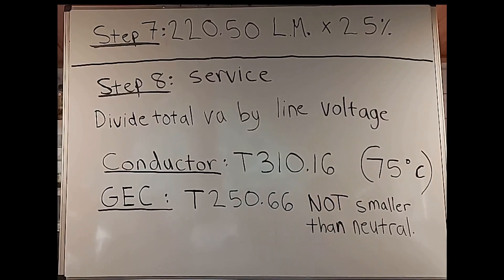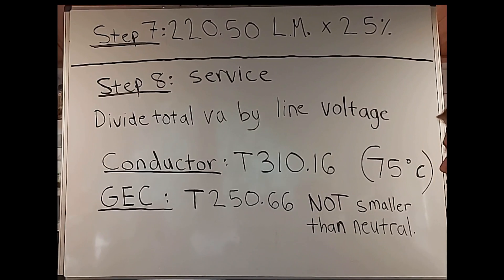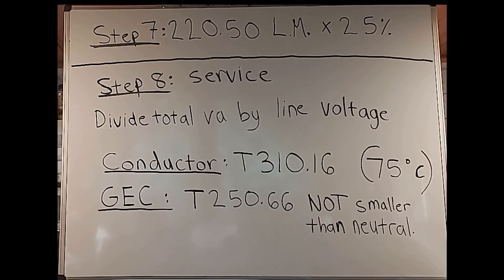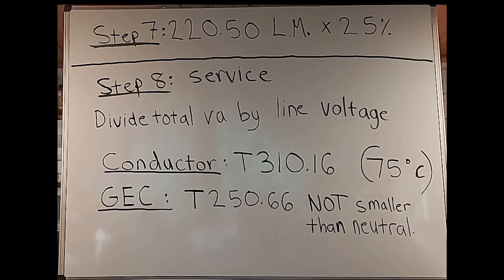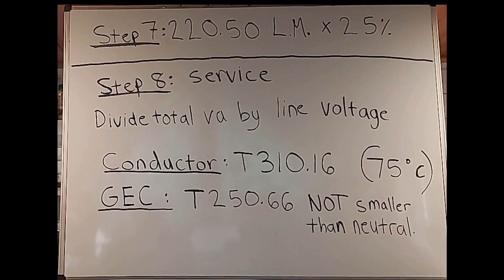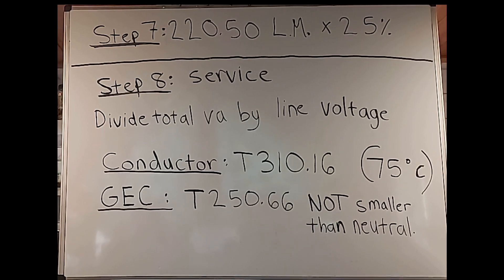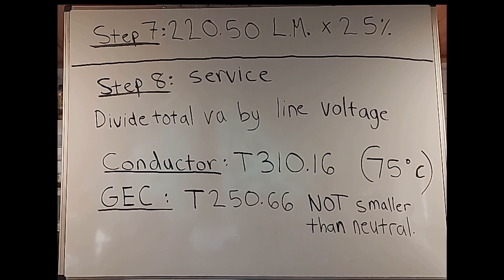Now step seven is something we've done before, described in article 220.50. We're going to take the largest motor and multiply it by 25%, then add that number one time to our load calculation. Step eight — which is basically the last real step — is adding everything together for the service, with some very important information on how to do that.